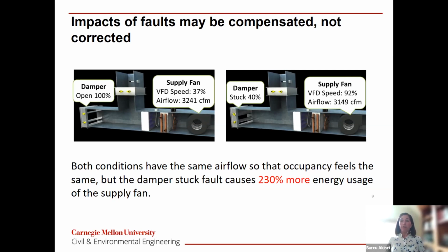When there's a fault in the damper, which happens pretty regularly, the dampers get stuck — let's say in this case the damper got stuck at 40%. The supply fan, by definition, because of the control logic and requirements, is still trying to provide the same airflow to the room, but now working at 92% speed.